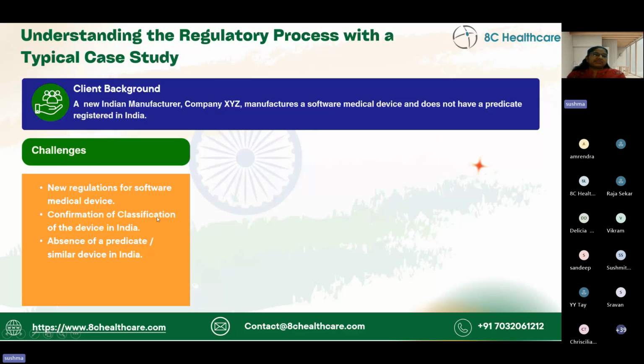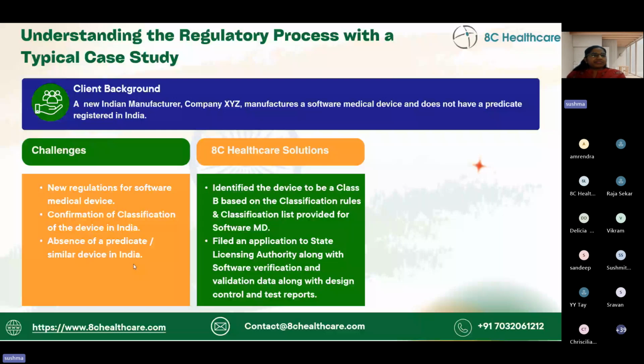And confirmation of the classification of the device in India was also very doubtful for the client. Because of the absence of a predicate or similar device in India, the client was uncertain whether they had to go for a clinical trial or file a manufacturing license in India. With these challenges in mind, they were not sure how to proceed further. So they reached out to 8C Healthcare, and these are a few of the solutions we gave to the manufacturer. We identified the device as class B based on the classification given by CDSCO for software medical devices.